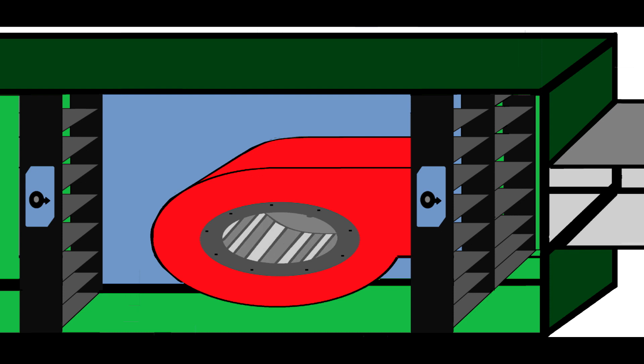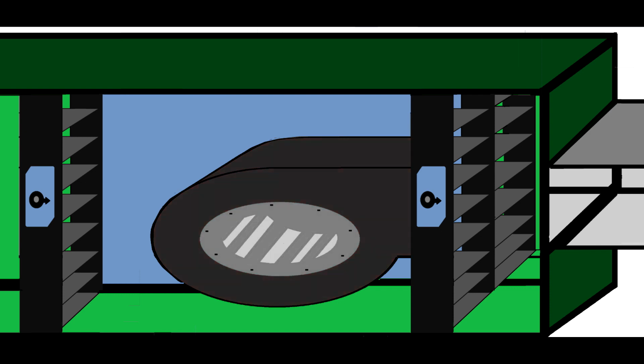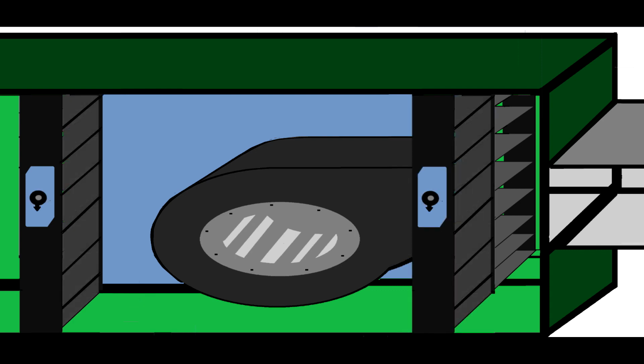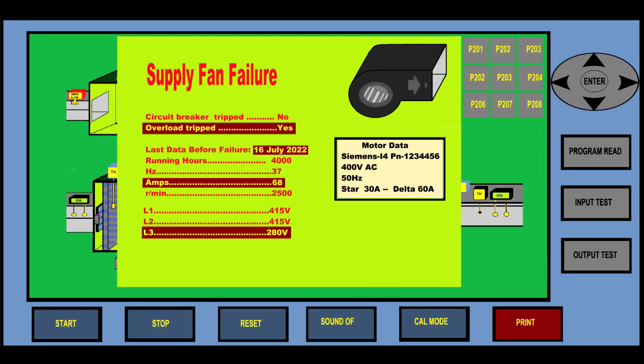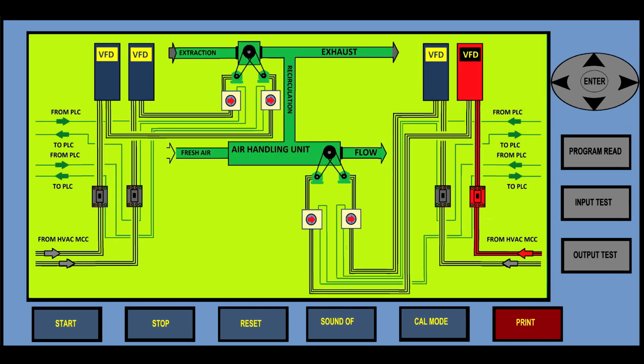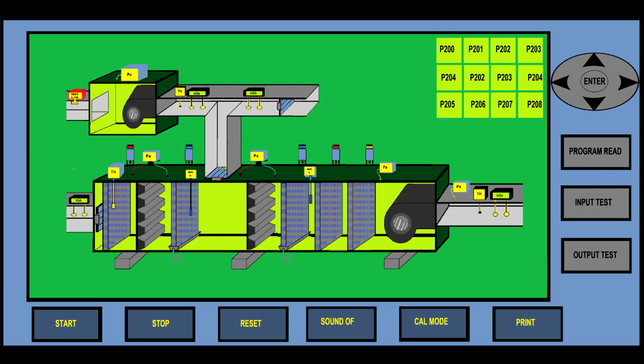Sometimes the fans can stop, but they will not be faulty. The electrician is inclined to go and check the fan motors, but the programmable logic controller will do a self-assessment, and the HMI will display the fault. So this type of failure will be picked up by the PLC. The motor which is still healthy will take over and accelerate to compensate the capacity. But this time, as you'll see, you have a supply fan failure, and you have the L3 power supply at 280 volts. Now the HMI will show you to check the power supply to the VSD. So it is not the motor. Actually, this intuitive system has the capability to tell you what's wrong, to guide you correctly on what to check and where. And if you do this, you'll have a healthy AHU.